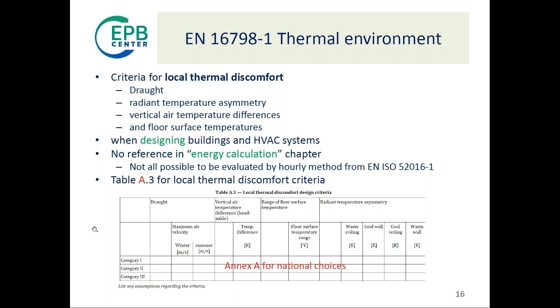There is also a possibility, especially for rather high operative temperatures above 25 degrees Celsius, that increased air velocity could be used to improve thermal comfort. So if you feel hot, it may be a relief to have increased air velocity from a fan that blows to your face or body. This is mentioned as well in the standard. You see again an Annex B table with some values, and an Annex A table which is empty, where values can be set on a national basis.